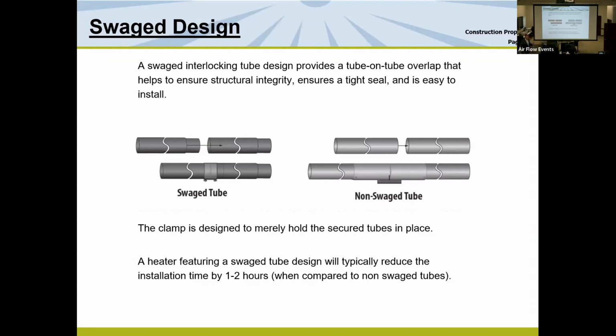And on every start and stop cycle, when the heater turns on and turns off, moisture forms, okay, because it has to get above and below the boiling point. And if you have a gap where the clamp is, that's where moisture is going to form. You're going to see early corrosion and failure. Sell our swaged tubes. We put a lot of work into having to do that. Make sure people understand why. Next slide.